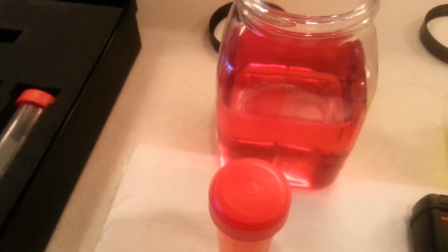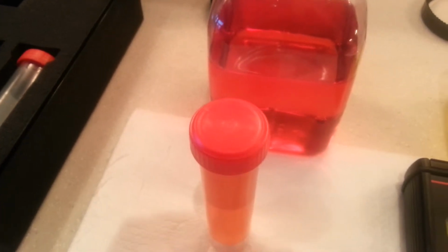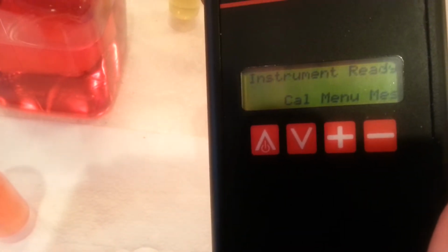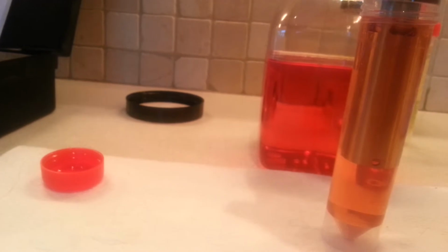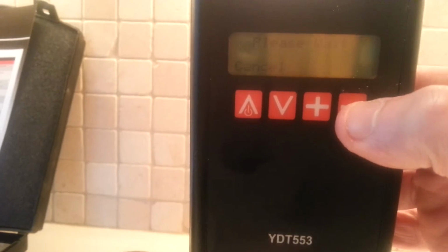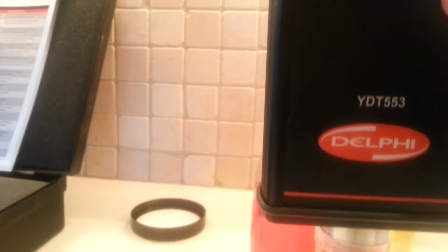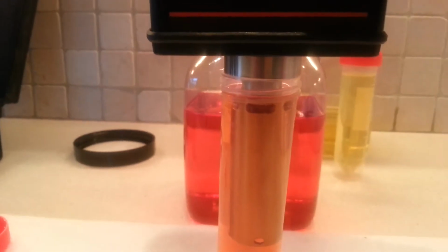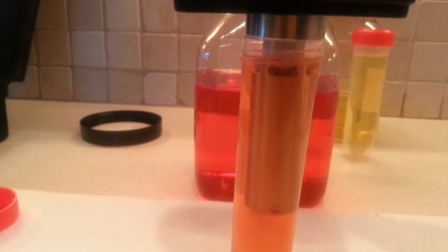Well, we've got the sample ready. We'll take a test then of our commercial red diesel. See you shortly. So the probe has been cleaned and it's been recalibrated. So our calibration, we can now exit from that, and we're now ready for our measurement. So like before, we rest it on the neck of our sampling bottles that you get with it, and all we need to do then is just press measure, and it's the same period of time, 20 odd seconds, the audible alarm, and then we leave it for 50 odd seconds and it gives us a count of percentage.